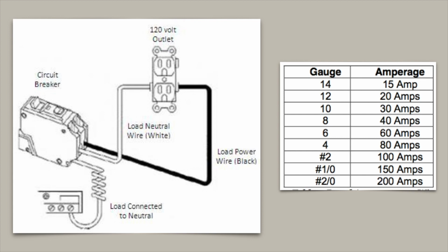The branch circuit breakers protect the branch wiring going to the different devices in the rooms of the house. These are generally 14, 12, or 10 gauge wires. A 14 gauge wire can safely carry a 15 amp load. A 12 gauge wire can handle a 20 amp load.